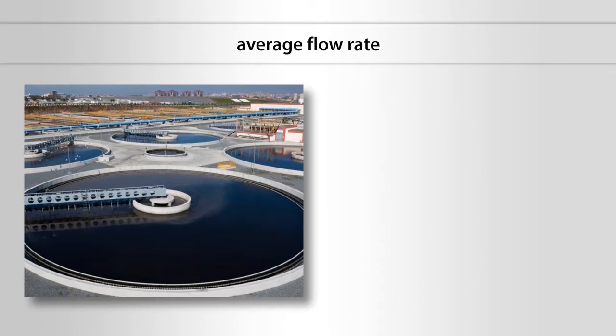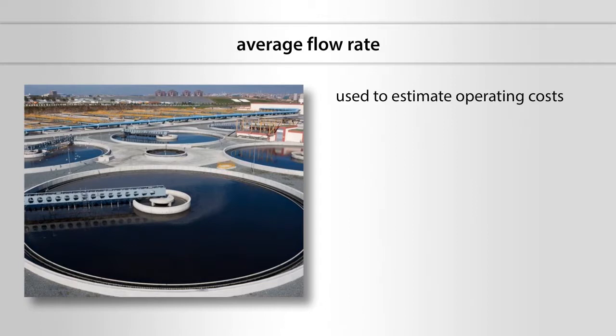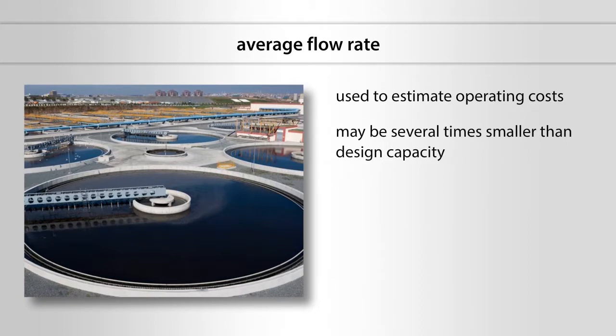An average flow rate should also be determined, which will be used to estimate operating costs. Costs such as chemical and power usage depend upon the actual gallons of water treated, not the capacity of the plant. The average flow rate may be several times smaller than the design capacity. For example, it is not unusual for a water treatment plant with a design capacity of 1000 GPM to have an average flow rate of 300 GPM.